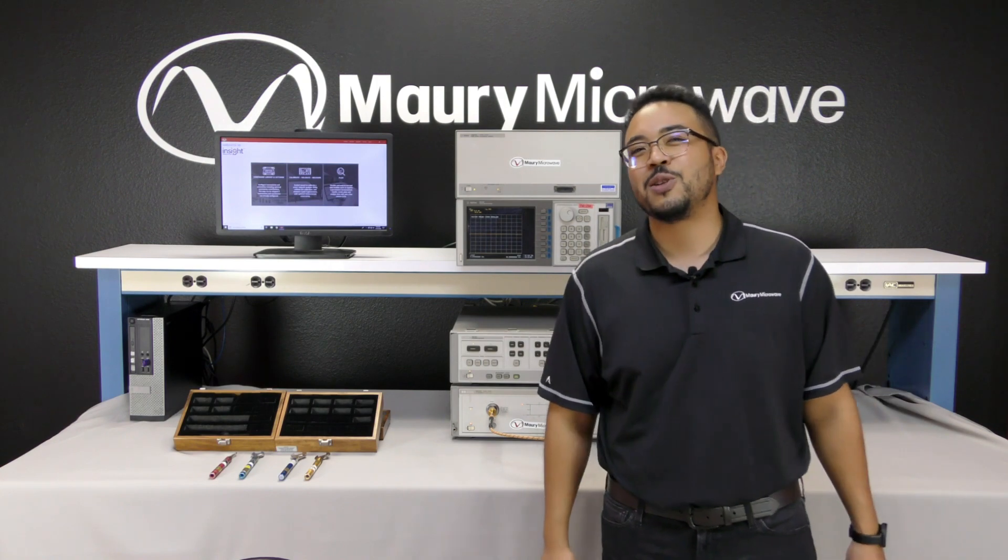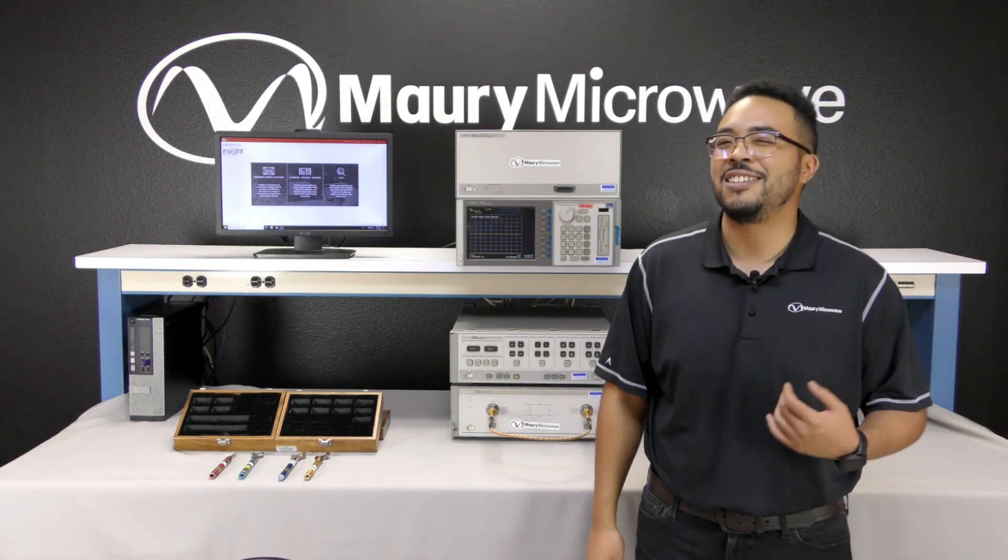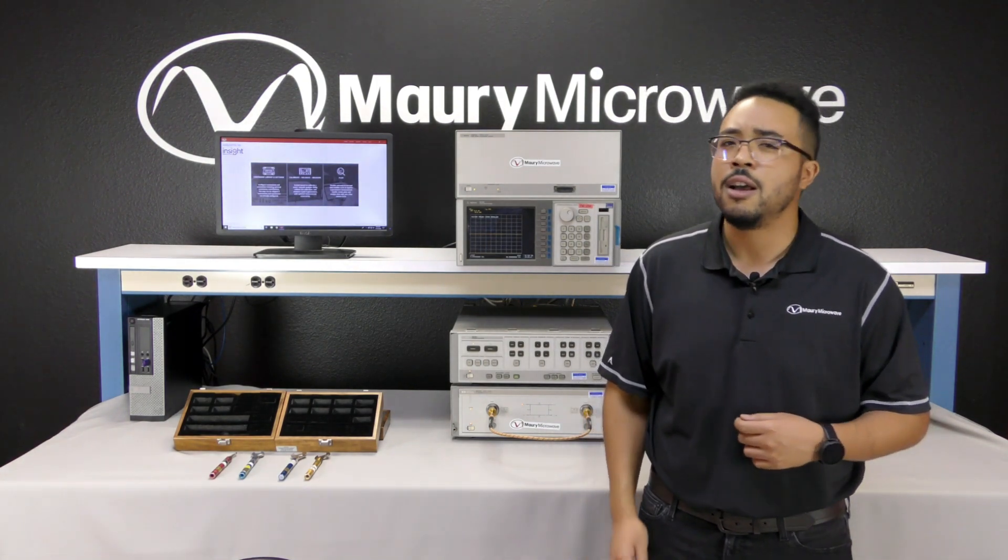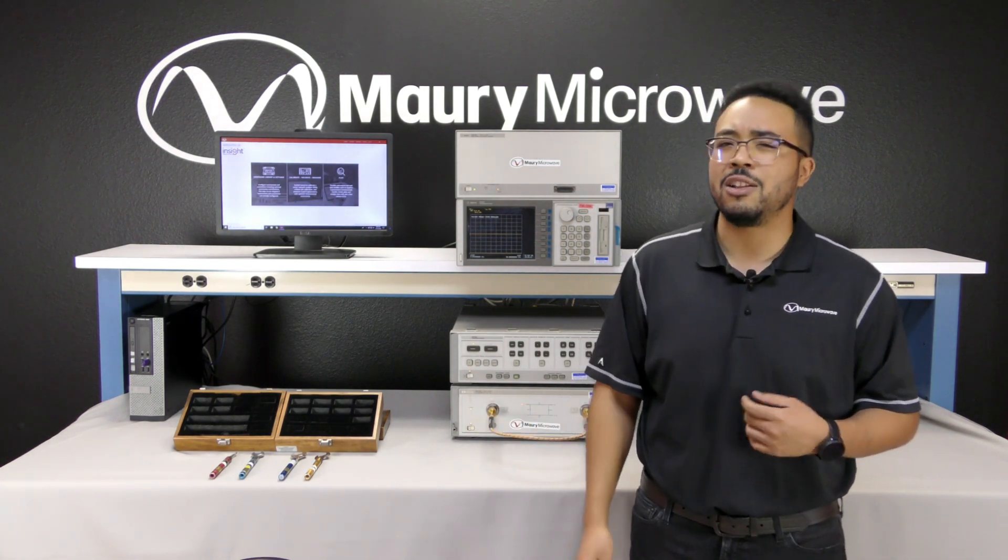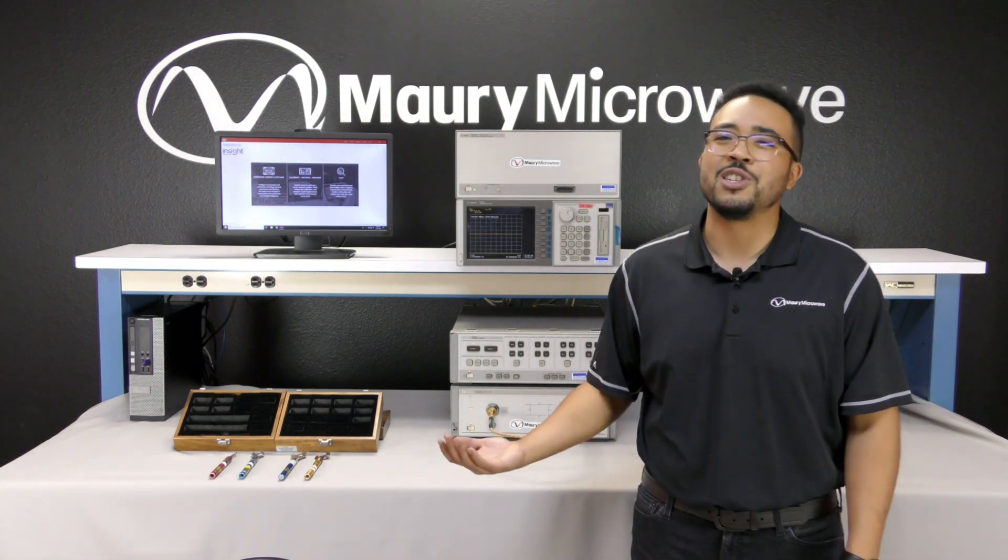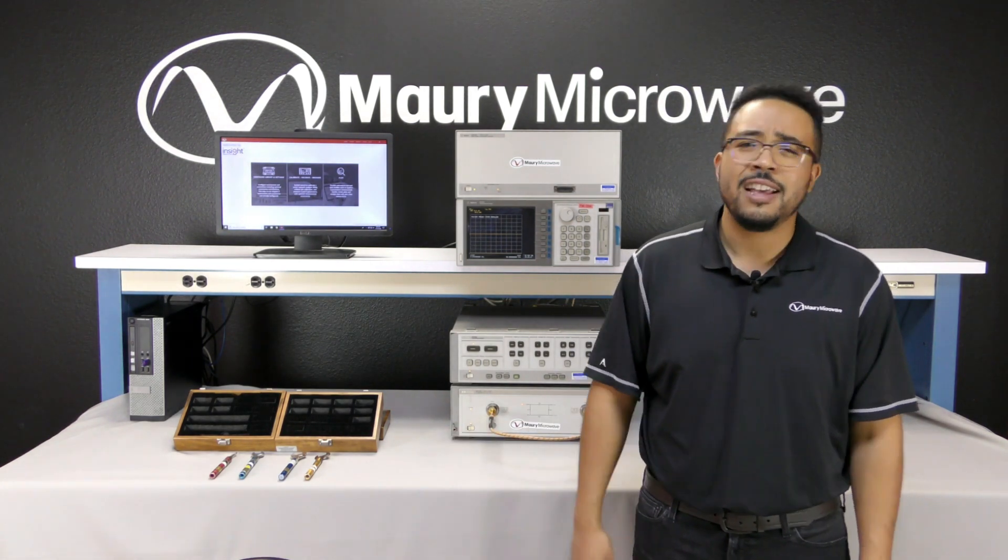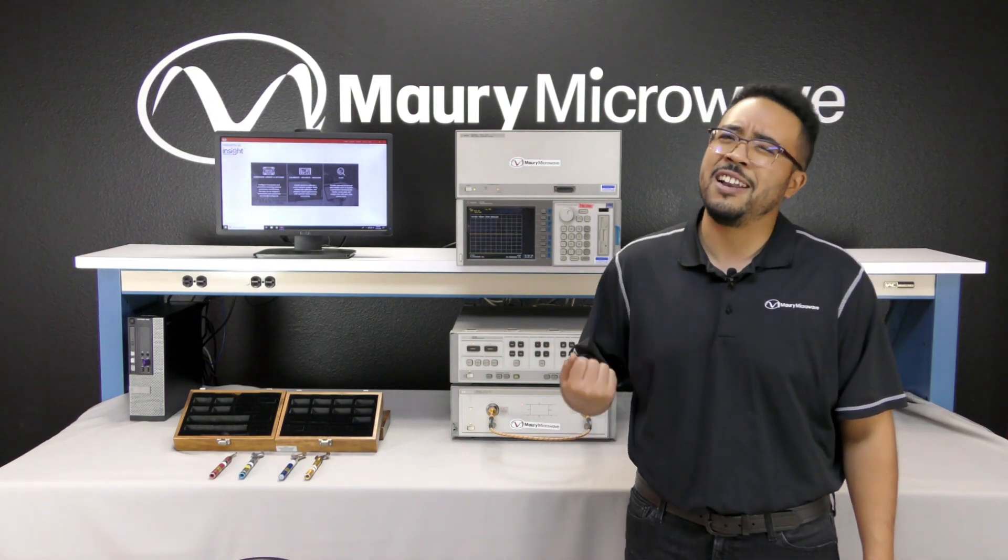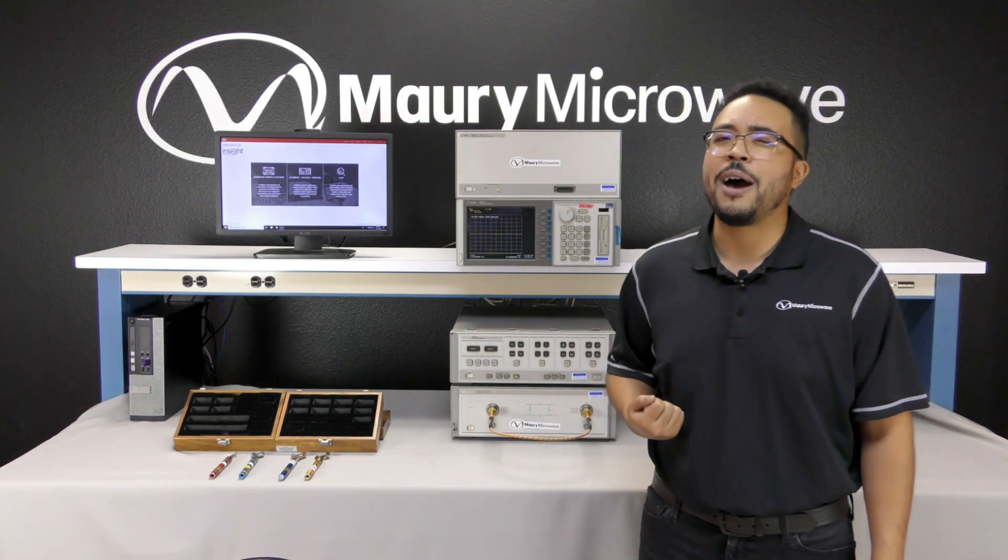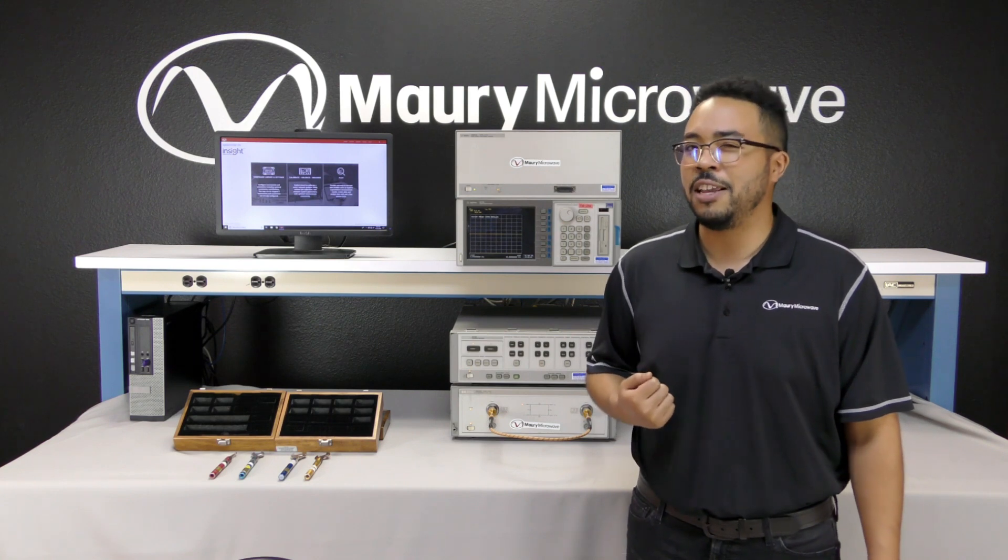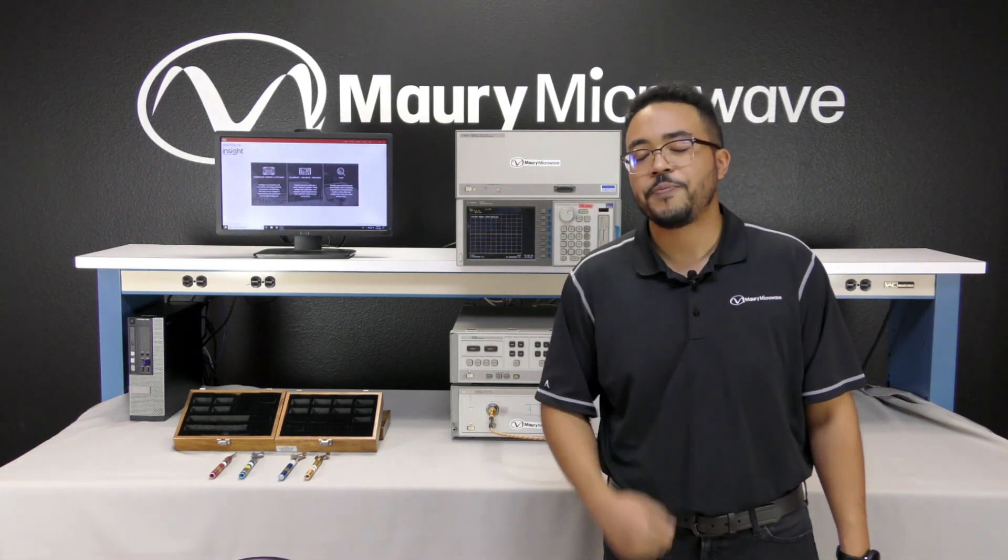Being 35 plus years old, these units may show age such as damaged or non-functional hard keys, obsolete cartridges and diskettes to load cal kits, dead or damaged displays, lack of a modern interface which can be kind of clunky to use, a lack of compatibility with modern calibration techniques, and finally, lacks the paradigm of uncertainty.